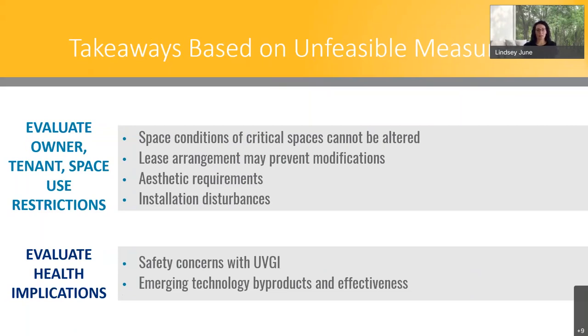And then finally, evaluating health implications is also important. So as I mentioned before, there are safety concerns with UVC exposure to humans. So ensure that any in-room application does not present exposure potential and that safeguards are in place for maintenance activities for systems in units. And then look for third-party unbiased testing results that are applicable or relatable to COVID-19 when considering any emerging technology. And this is to ensure that there are no harmful byproducts and the technology is effective for its intended use. Next slide.